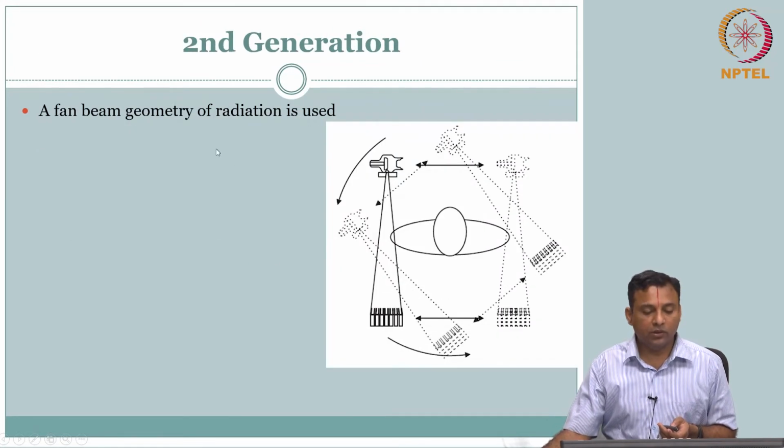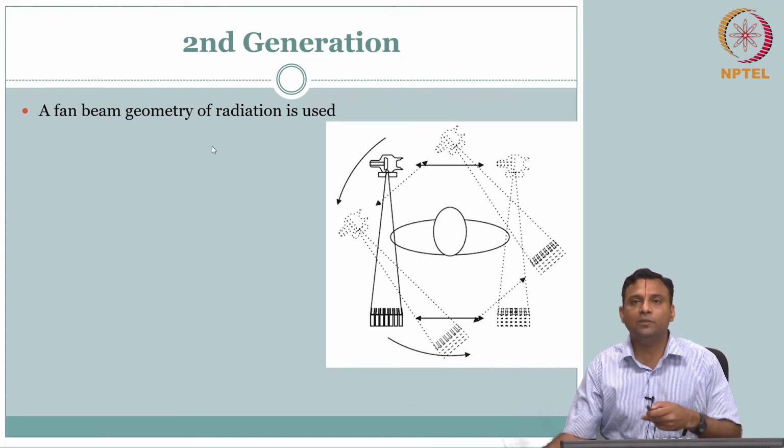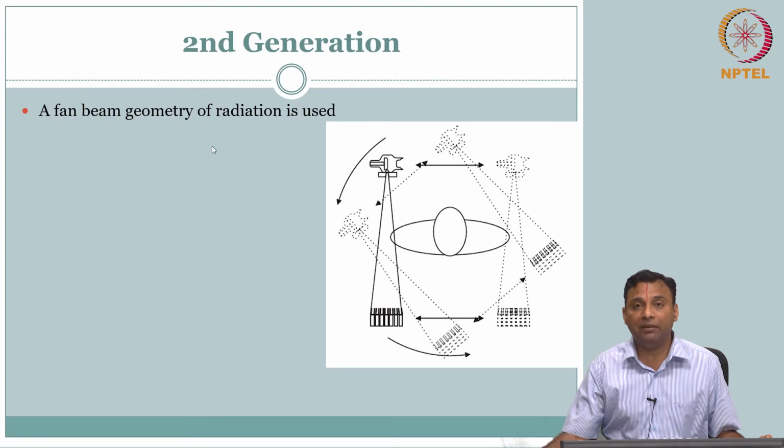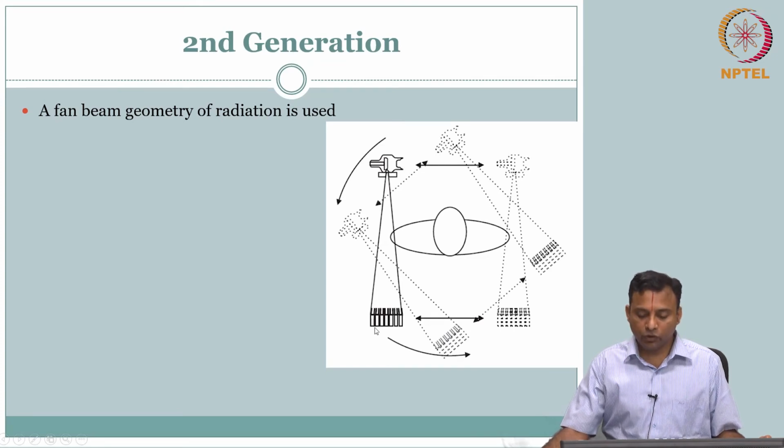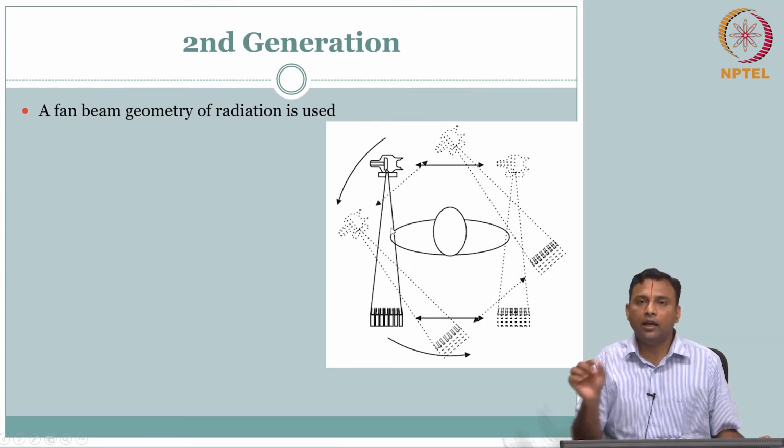Okay. So at that point of time, if you are the engineer and you have worked out this ecosystem, one of the major bottlenecks could be, oh, your acquisition time is of the order of minutes. How do I reduce it? Can we improve that further? Instead of having one detector, can I detect simultaneously with a few more detectors? Therefore, I can reduce the number of rotation steps I need to do. So they had a few more detectors next to each other. Of course, instead of a pencil beam, we wanted to send a small fan.